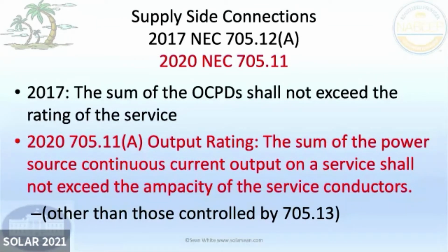When we're doing a supply side connection, let's say in the 2017 NEC, the sum of the overcurrent protection devices, that's breakers coming from the supply side connection, cannot exceed the rating of the service. Those are the wires between the main breaker and the meter, and it can't be bigger on the other side of the main breaker either. In 2020, you can even put more. The sum of the power source continuous current shall not exceed the ampacity of service conductors. Before, you were comparing the overcurrent protection devices to the service. Overcurrent protection devices are oversized for safety by at least 25%. Here we're just saying the output power of the inverter can't exceed the service conductors. That's getting kind of close to the edge.